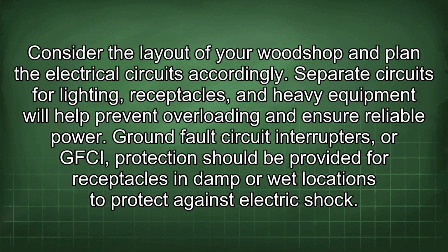Consider the layout of your woodshop and plan the electrical circuits accordingly. Separate circuits for lighting, receptacles, and heavy equipment will help prevent overloading and ensure reliable power. Ground fault circuit interrupters, or GFCI, protection should be provided for receptacles in damp or wet locations to protect against electric shock.